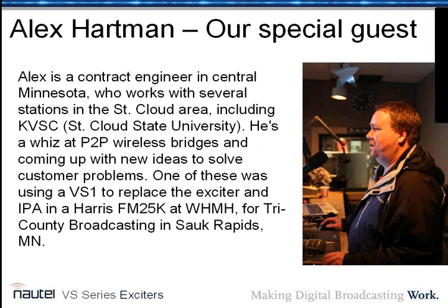That's right. One of the other things you'd mentioned, Alex, and I'm going to borrow a phrase you'd used a couple of minutes ago, breathe new life into an old transmitter. On the FM25K at WHMH, as I recall during the install time, you specifically mentioned something about the output power on it. Yes. Like I said, it got a little more efficient and everything went happier. The transmitter's starting to idle. It's not pushing as hard as it had to before.